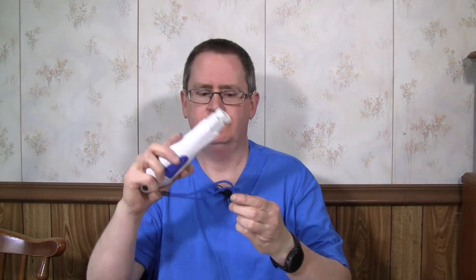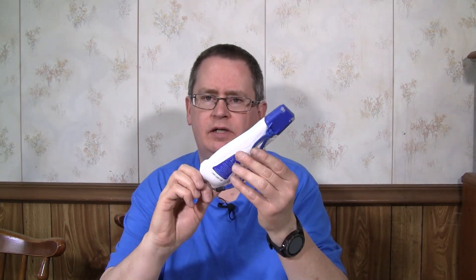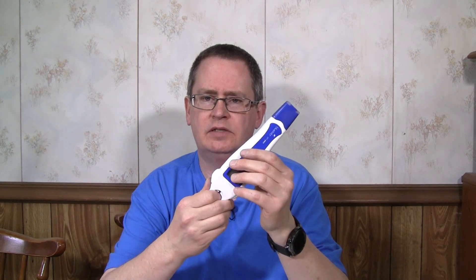I've been using this Blue Labs pen and it worked really well when it worked. I got it about two years ago and just recently I tried to calibrate it and it's giving me an error. I did all the things you're supposed to do — soak it in storage solution overnight, cleaned the probe and everything. I contacted their support and they basically told me that after a certain time the probes just wear out, and these are not replaceable probes. So when it stops working and you've tried everything, these are basically disposable — but they're fairly expensive. I think the cheapest you can get them is around $80, but they sell well over $100.